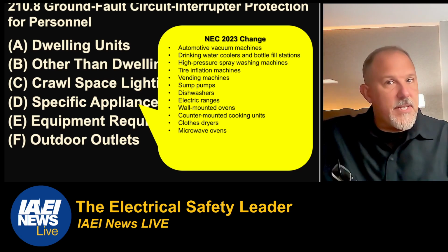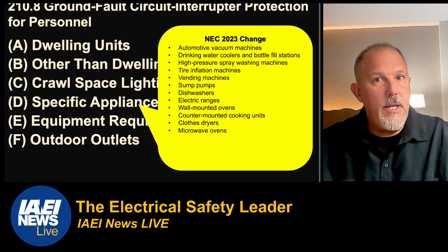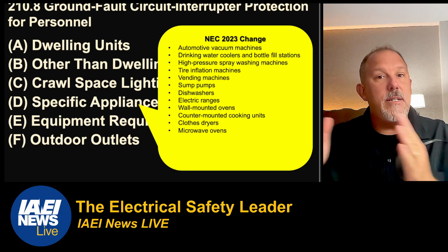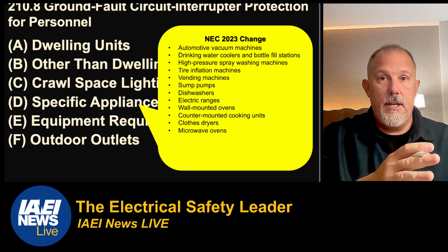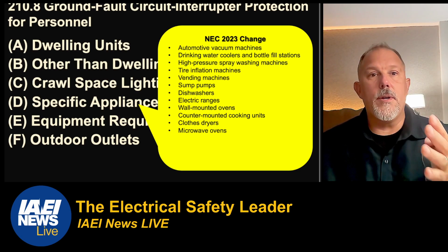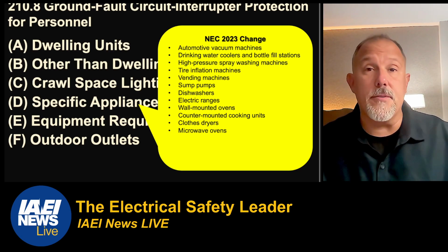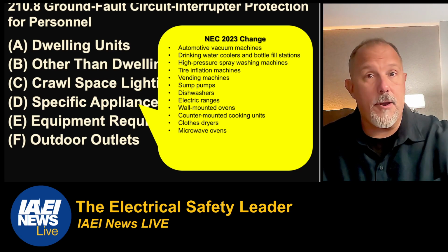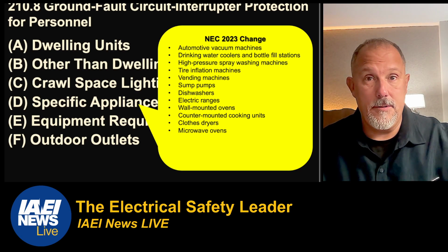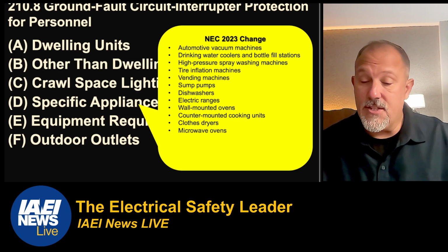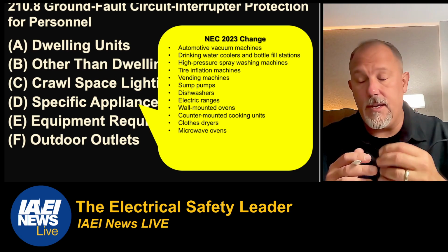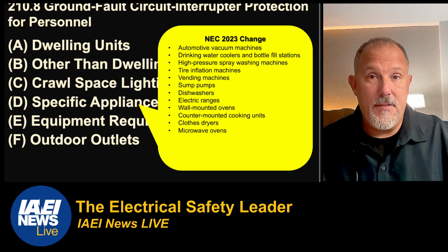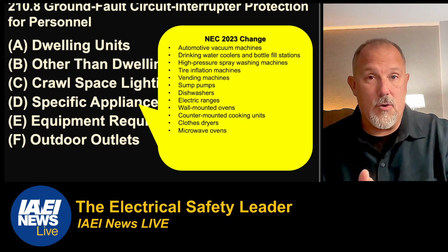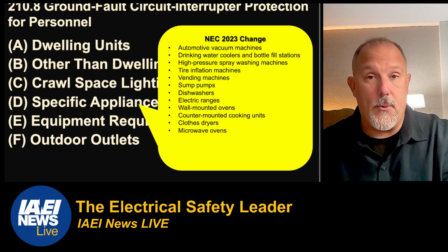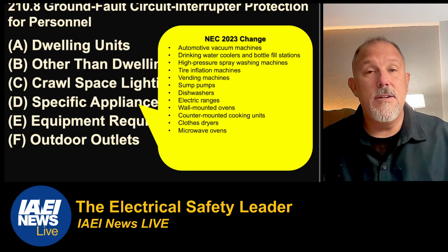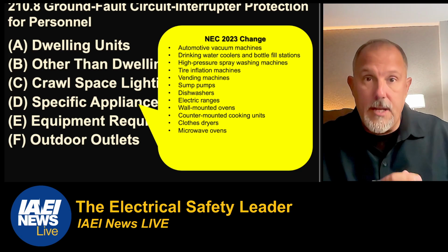And remember the discussion earlier that we saw in 210.8(B). They made a change in 210.8(B): the distance from the appliance to the sink. Now, one of the code panel members during our discussions accurately pointed out that you don't need water. You don't need proximity to water to be electrocuted on this equipment. And it's not just the failure of this equipment that drives the deaths, the GFCI requirement, or the data point of deaths.